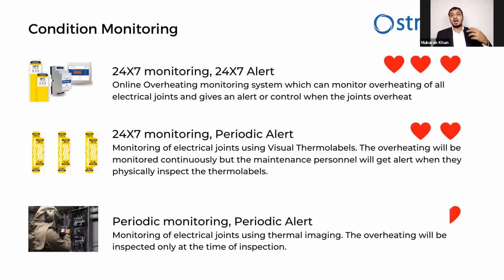I have given hearts to each method depending on how much I like it. You can give the hearts depending on how much you like it. Maybe 1 like, 2 likes, 3 likes, depending on your interest. So the one I like most is 24/7 monitoring with 24/7 alert. It is done through an online overheating monitoring system, which can monitor overheating of all electrical joints and gives an alert or control when the joints overheat. Then the second, which is a little bit lower than the first one, is 24/7 monitoring and periodic alert.